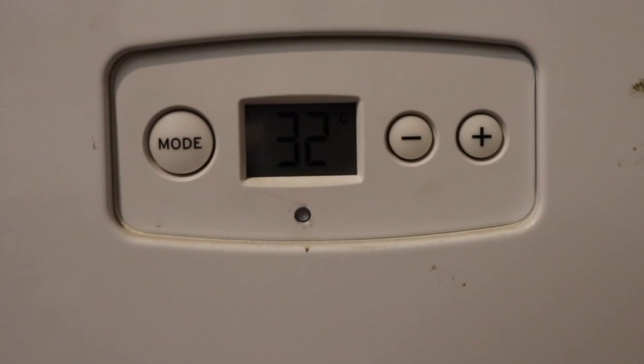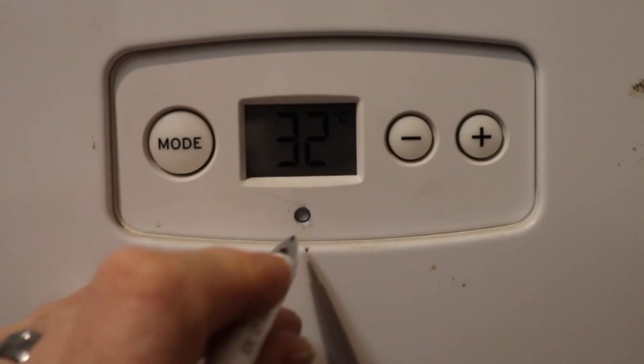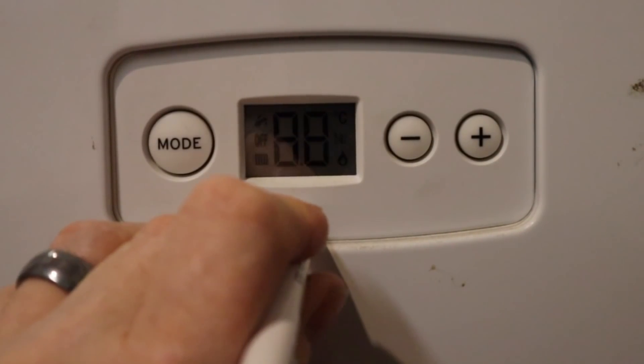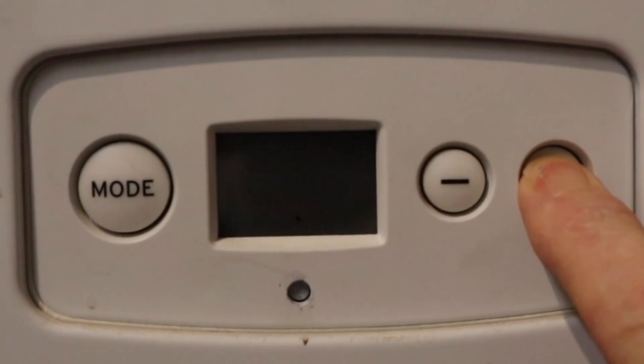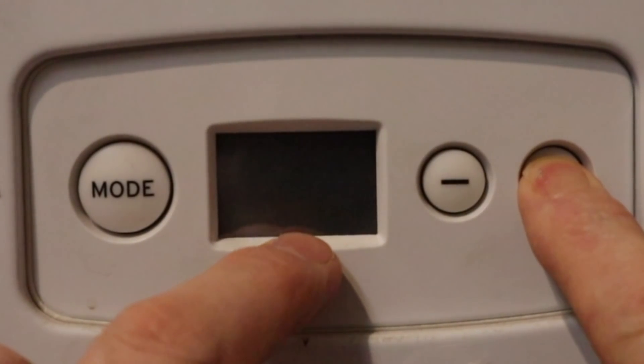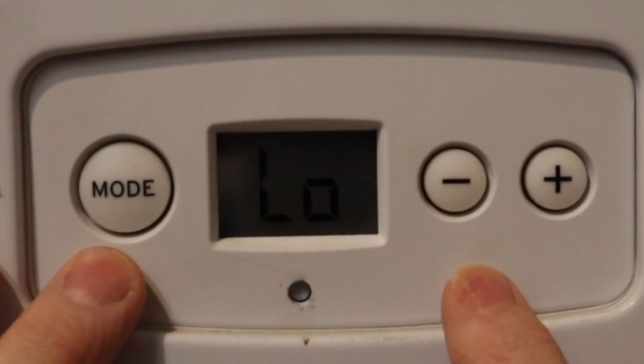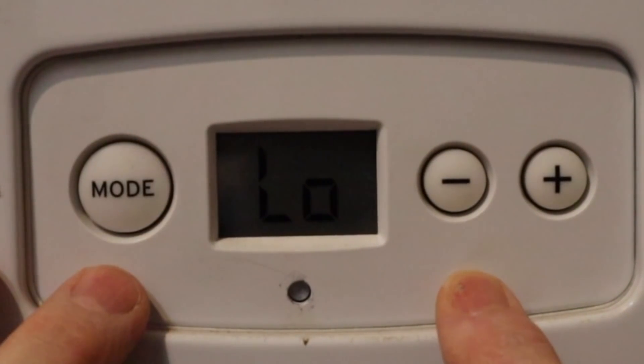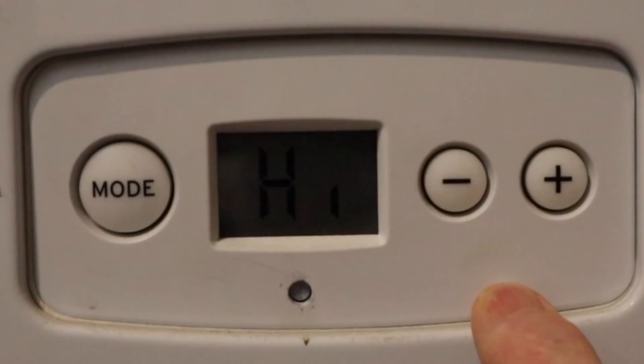The boiler we have here is the Glowworm Flexicon 24 CX. Putting this in high and low fire is a bit fiddly. Press the reset button, let go, and immediately press the plus button. You can see a little dot comes up with an H, indicating it's now in the high setting. To put it in low, press the minus button and then press the mode button and it'll go into low setting. Press the plus button to put it back in high, then press the mode button to accept.